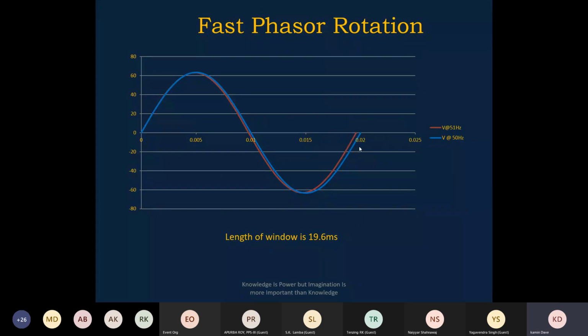Similarly, for the fast phasor rotations, if it is 51 hertz, you look at it here, it is a 19.6 millisecond window. If 50 hertz, it is a 20 millisecond window. The window is now reduced in that case, so it is a faster rotation. Why? Because when there is over frequency in the system, the devices have to measure the correct frequency according to the windowing system. So that frequency tracking has to work properly.